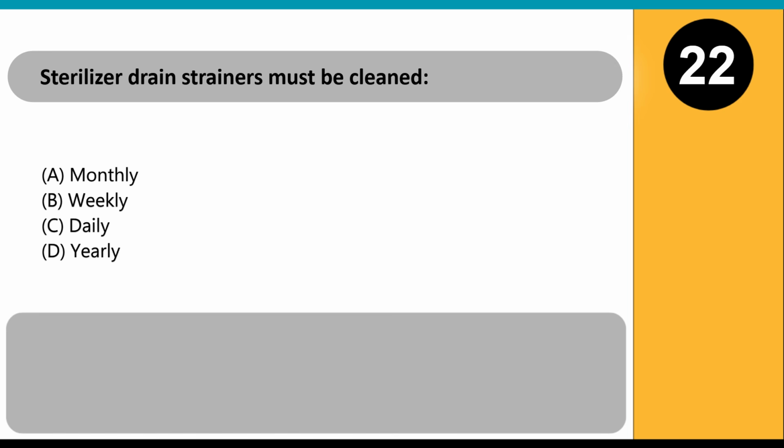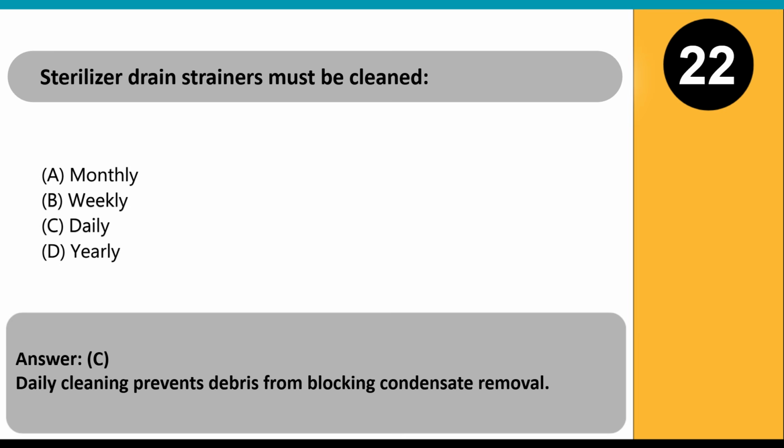Sterilizer drain strainers must be cleaned. A. Monthly, B. Weekly, C. Daily, D. Yearly. Answer C. Daily cleaning prevents debris from blocking condensate removal.